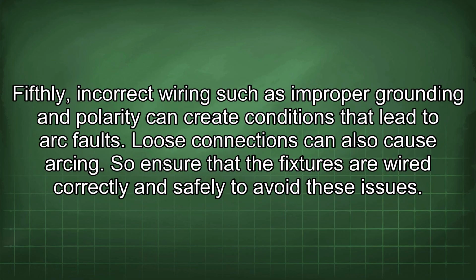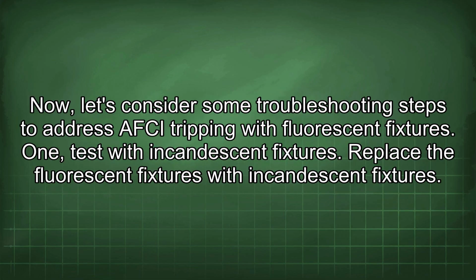Fifthly, incorrect wiring, such as improper grounding and polarity, can create conditions that lead to arc faults. Loose connections can also cause arcing. So ensure that the fixtures are wired correctly and safely to avoid these issues. Now let's consider some troubleshooting steps to address AFCI tripping with fluorescent fixtures.